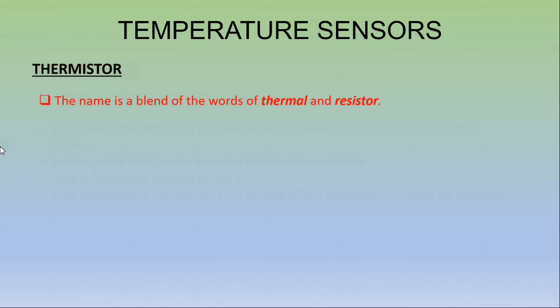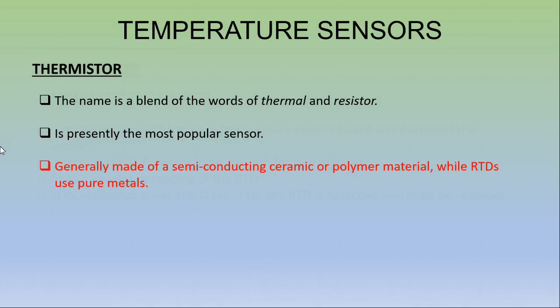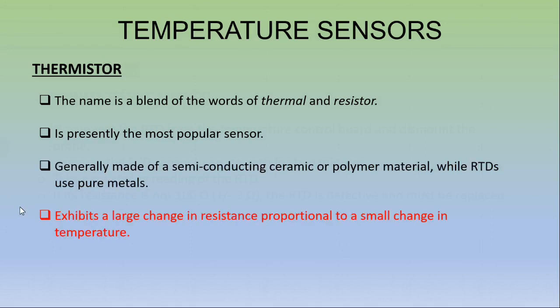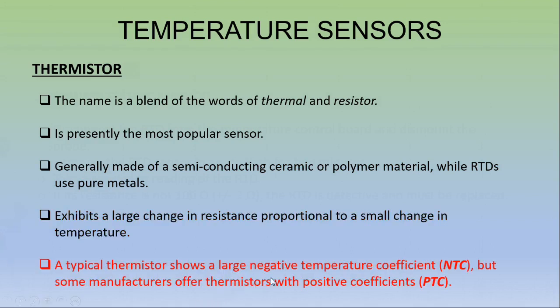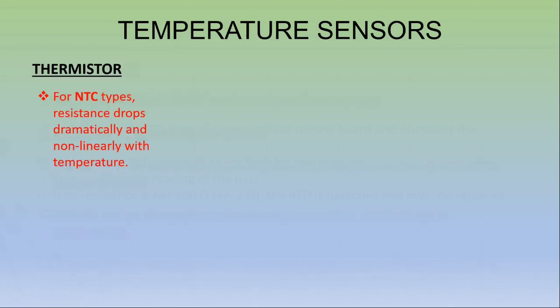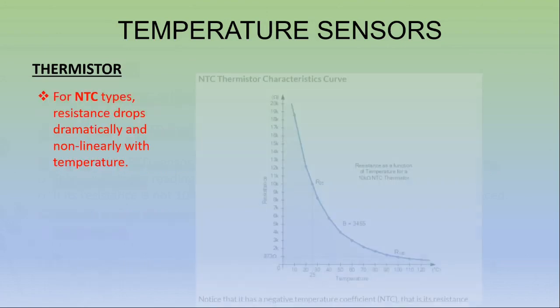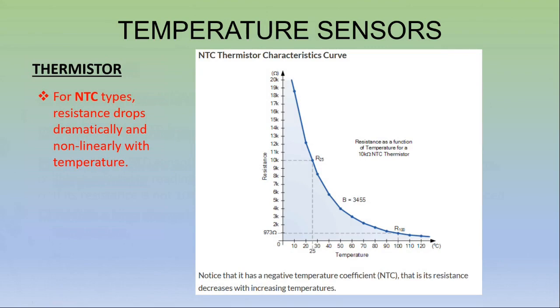And the third probe we're going to talk about is a thermistor. The name is a blend of the words thermal and resistor. It's presently the most popular sensor out there. It's generally made of a semiconducting ceramic and polymer material, while RTDs use pure metal. Thermistors exhibit a large change in resistance proportional to a small change in temperature. A typical thermistor shows a negative temperature coefficient, but some manufacturers of thermistors do offer positive coefficient thermistors as well. For NTC types, resistance drops dramatically and non-linearly with temperature.